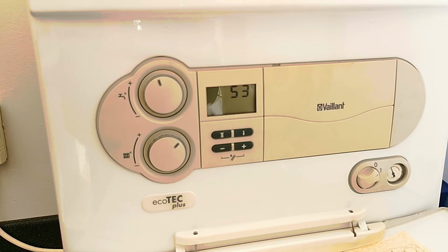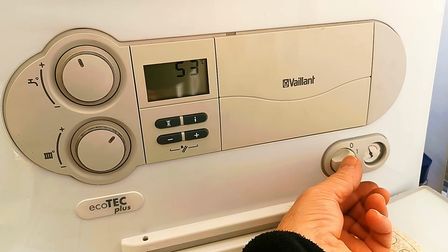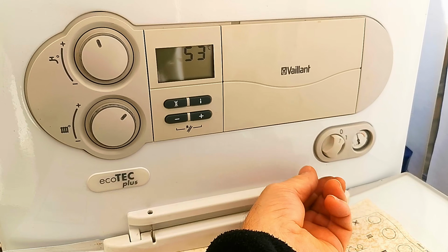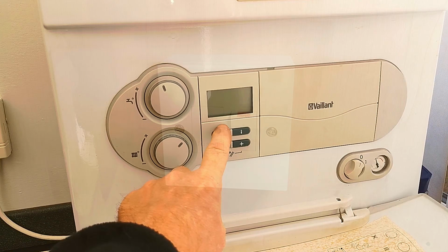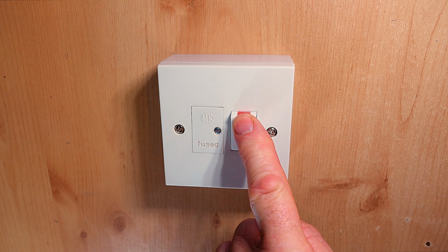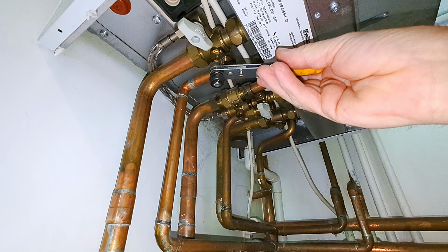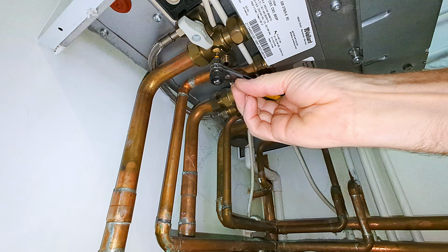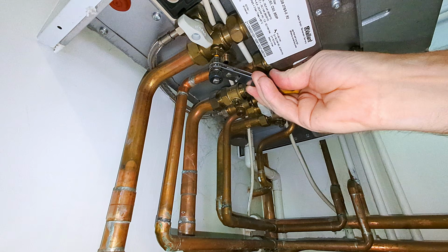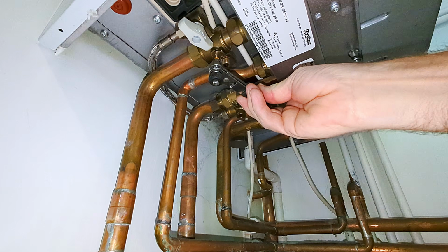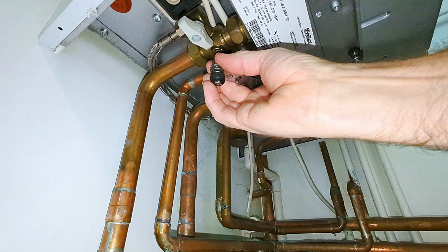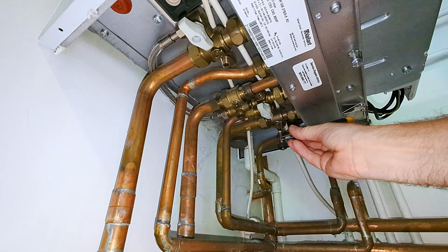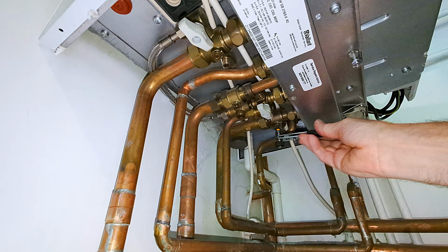So the first thing I'm going to do is to turn the boiler off, because I don't want the boiler running when I'm changing the pressure sensor. But the safest thing to do is always just turn the boiler off from the isolation switch on the wall. I'm then going to isolate the boiler from the rest of the system by closing both the flow and the return valves. That's the flow valve closed, and then I'm going to turn this valve over here and close that one. So now the return valve is also closed.